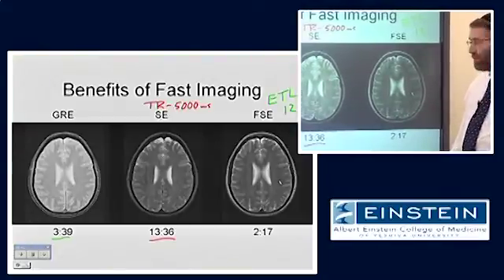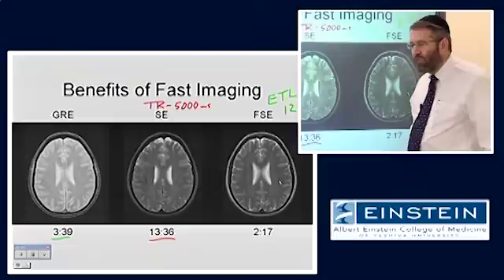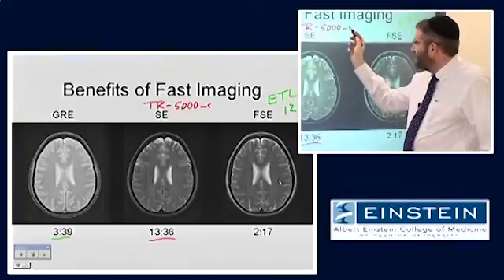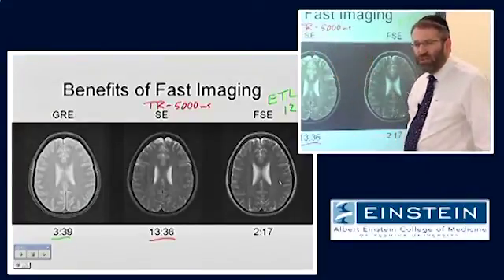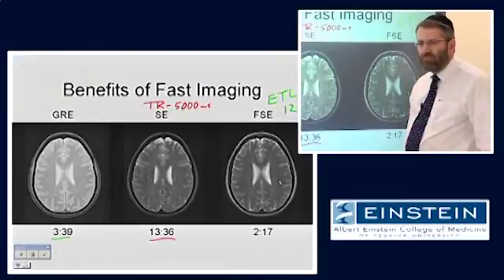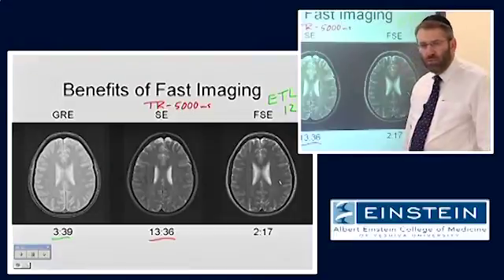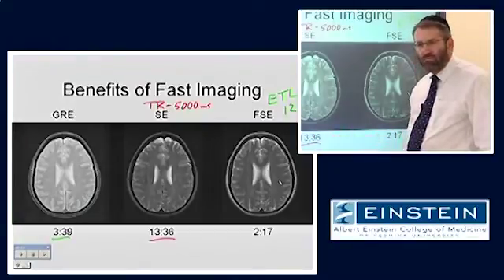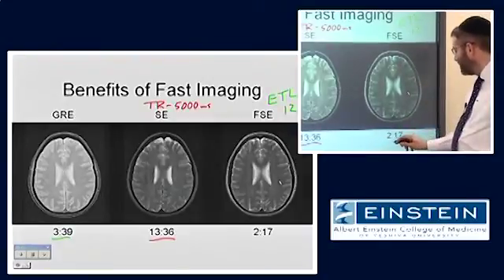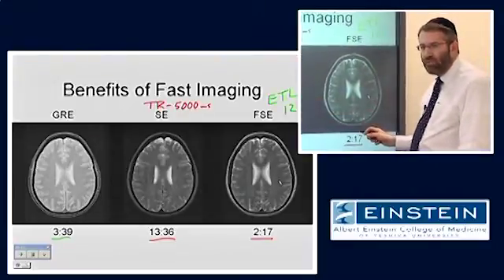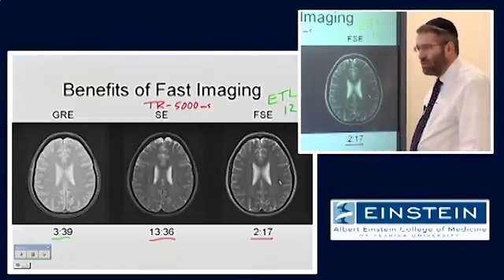We don't do spin-echo imaging. Even in the days before fast spin-echo — which is actually before my time — T2-weighted images were never acquired with a TR of 5 seconds because it just takes too long. But with fast spin-echo, we can get an image that has at least as good signal-to-noise, if not better, in dramatically less time.